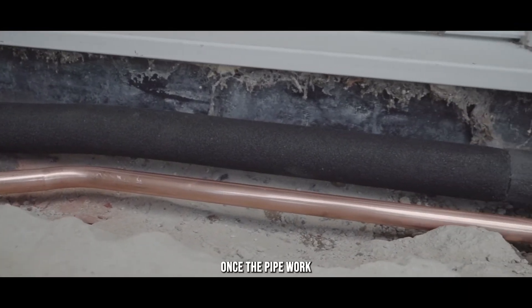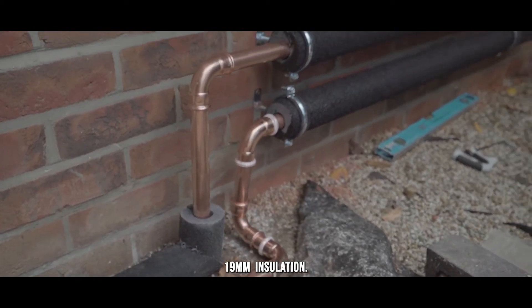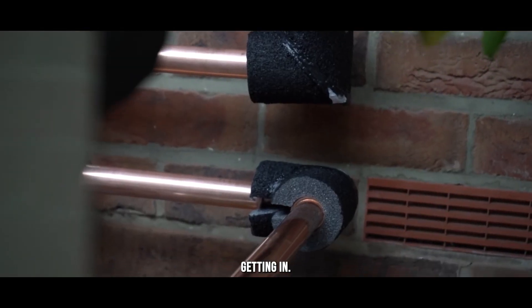Once the pipework to the heat pump is installed, we will insulate the pipework using UV protected 19mm insulation. All joints will be sealed to prevent heat being lost from the pipes and to prevent water getting in.